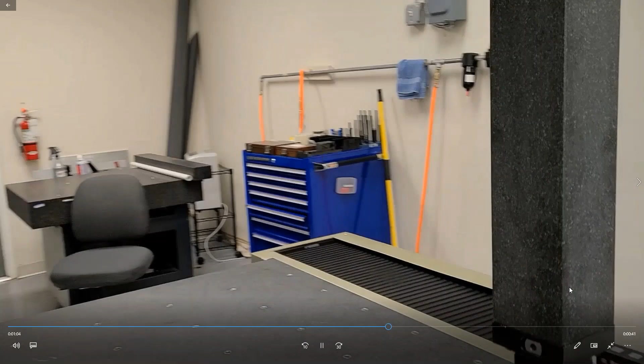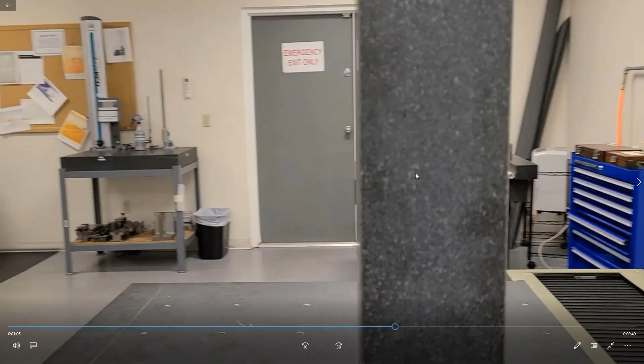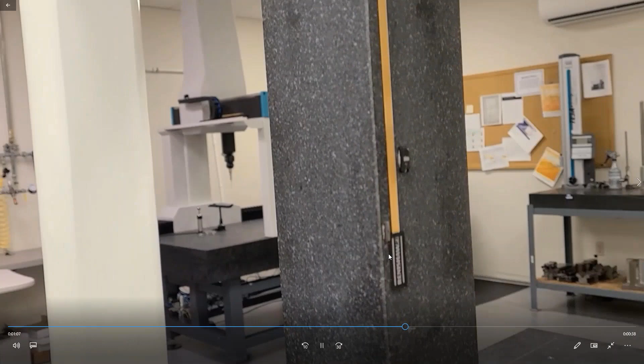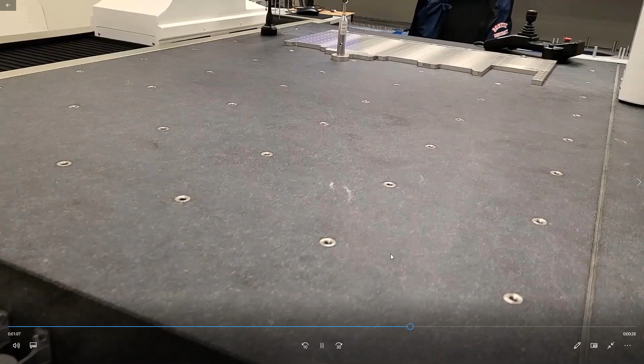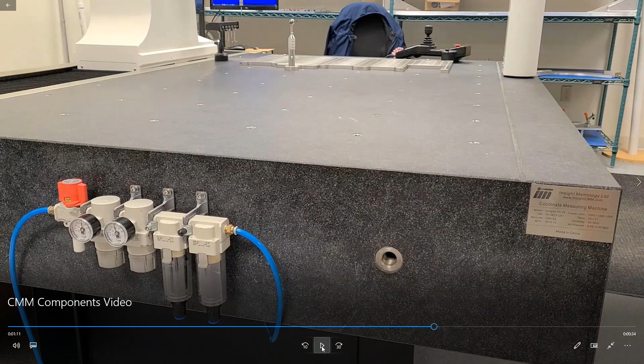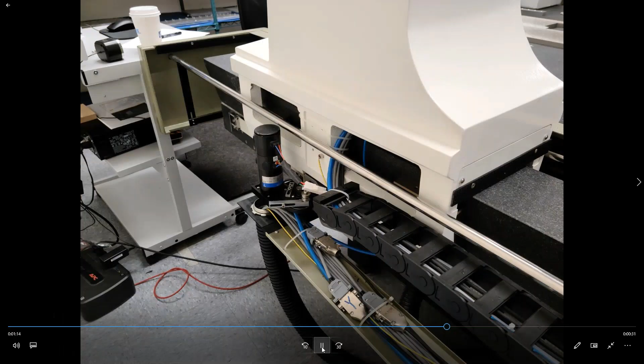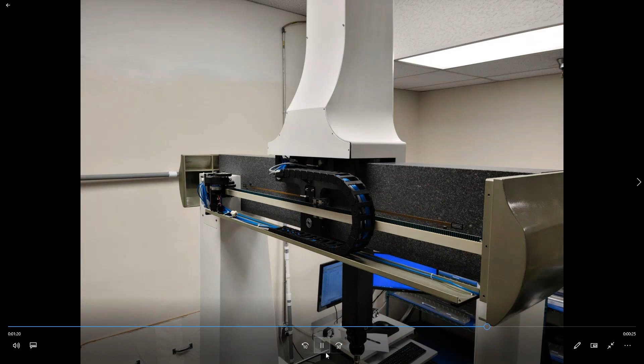You've got some other good views here too. This Z-axis happens to be granite as well. Sometimes there'll be aluminum. Here are the pneumatics in the back. You can see the air going in and out of the machine. It's got some pressure gauges, some filters. There are some additional filters on the wall where the compressor comes into the building. And I'll be going over some more of that later. Here's the Y-axis motor. Fortunately, serendipitously, a couple of days ago we were having our machine calibrated and worked on.